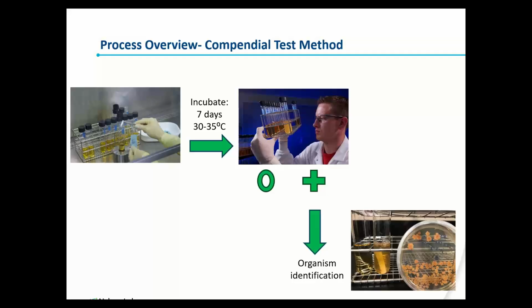After that incubation time requirement has been met, there's a visual inspection of the test containers to determine presence or absence of growth. And so you can see here in this image, there are some containers that look a little bit cloudy. So that usually shows up in the form of turbidity, some type of a film that grows. There can be like a debris or material that's present in the test container. And that visual interpretation and indication is how we decide whether the container is positive or negative for growth.